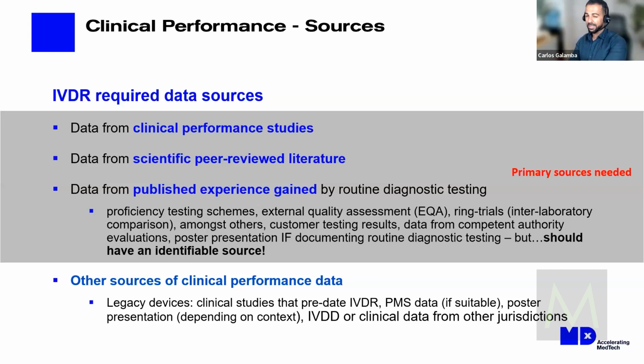So in most cases, it is okay, and I say this with caution, but one area where I see that being a real issue is, for instance, when you have near patient tests, because a lot of times, what is considered the near patient test user in Europe is different from a near patient test user in the US, because they have different qualifications. The actual people that can handle near patient tests, and tests done at the point of care, can be different between the two jurisdictions. So you would need to make that argument if you wanted to use US data.